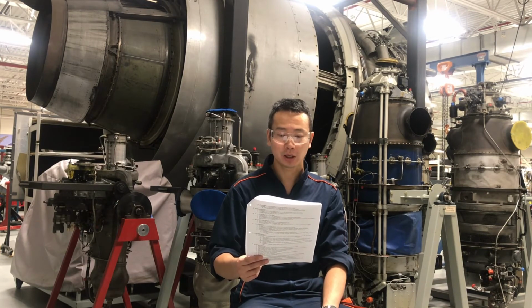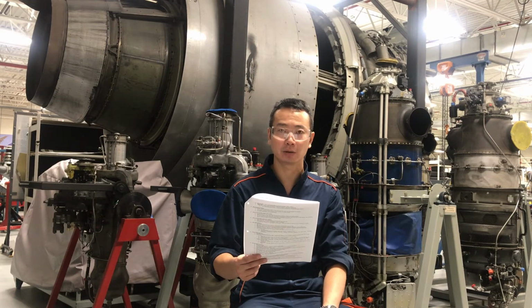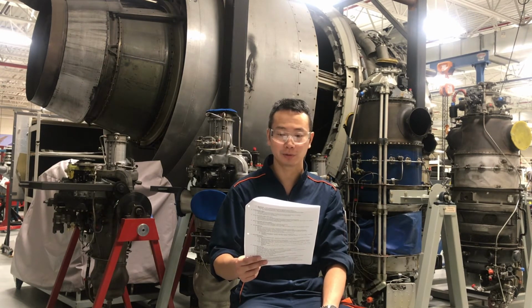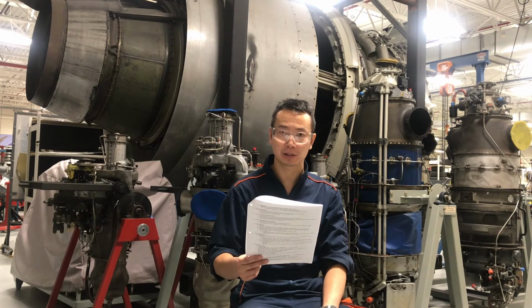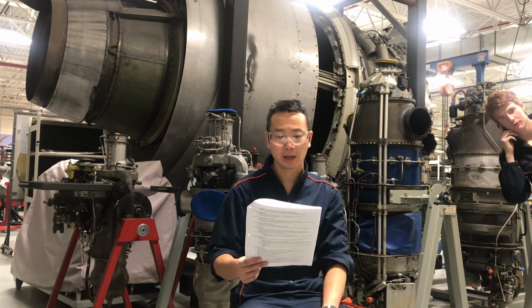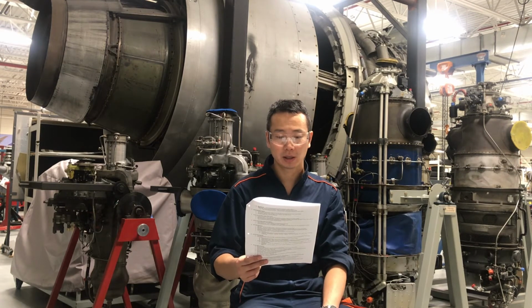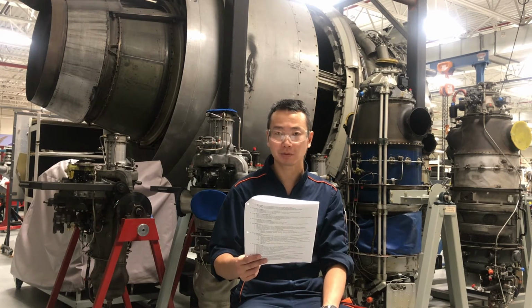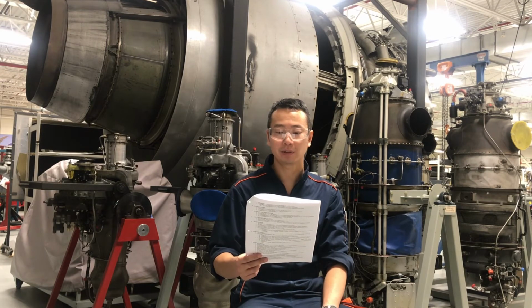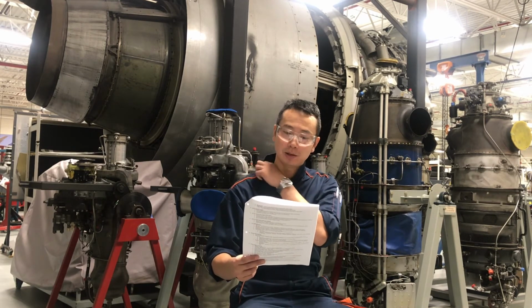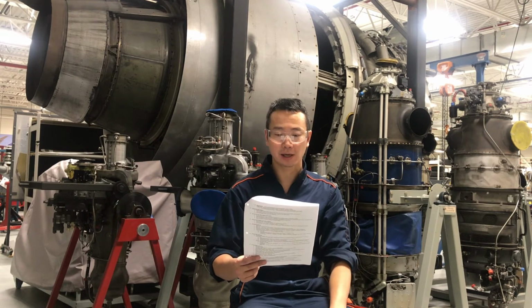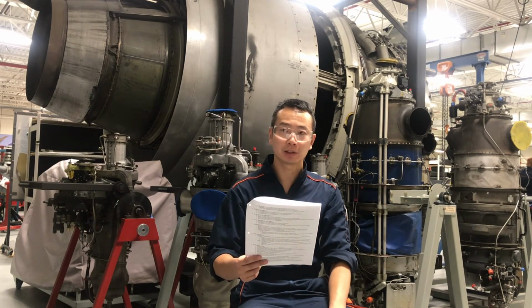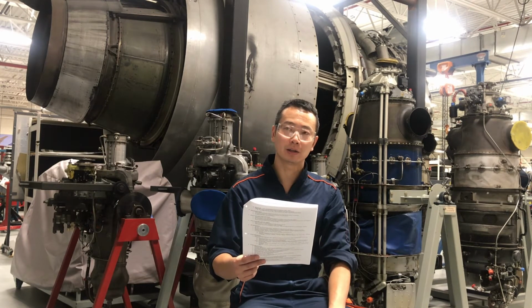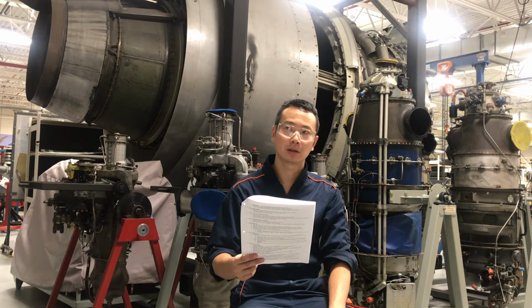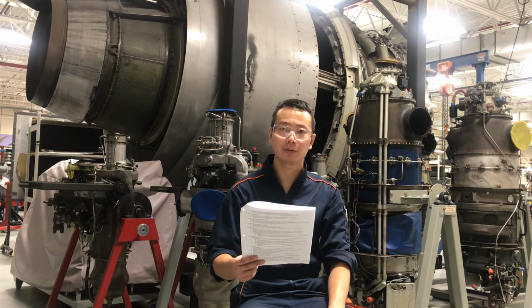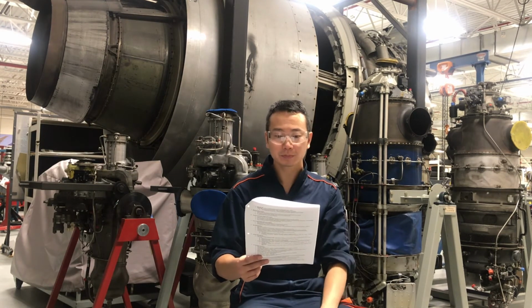The fuel switch is on, and you can tell the fuel flow from the indicator of fuel flow, and TIT rise, that means combustion happened and light off, and check the N1 rise, and 50% of N2 arrived, and it's at the speed of self-sustaining or acceleration speed, and after that the start air valve is closed and the ignition off.